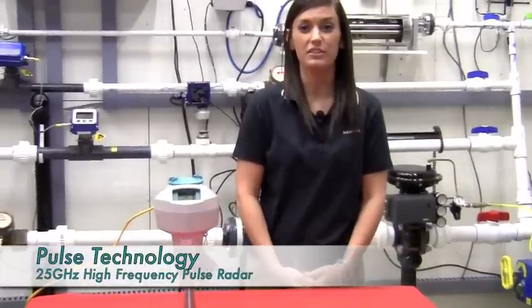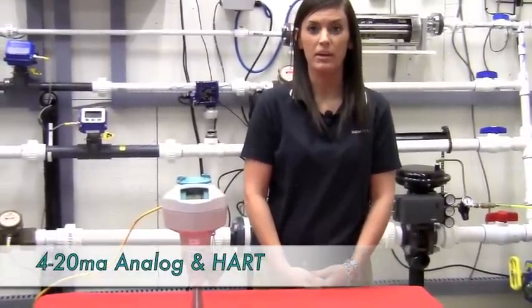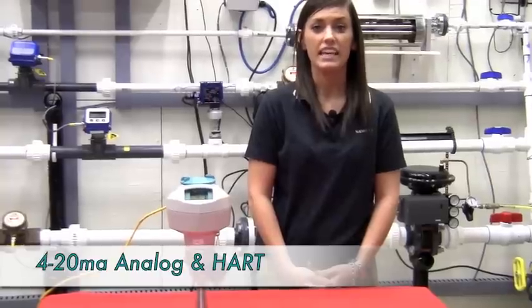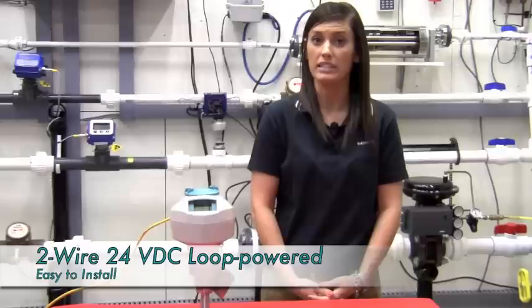It's a continuous level transmitter that uses pulse radar technology. It gives a 4 to 20 milliamp output and is HART smart. It takes 24 volts DC and is two-wire loop powered, which makes for a very simple installation.